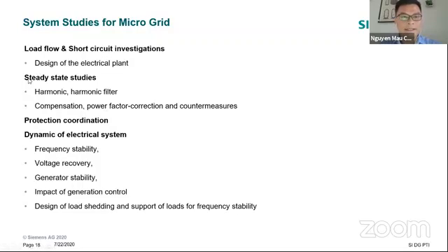And the other is the steady state study. We need to check the harmonics and the power quality, and if you have a power quality problem, you need to design the harmonic filter. And we need to see the reactive power compensation. We need to correct the power factor. And if you have a problem, we have to go through the countermeasures. Protection coordination is very important to protect your network against faults.